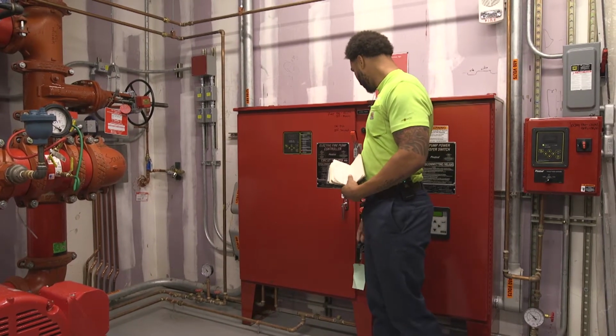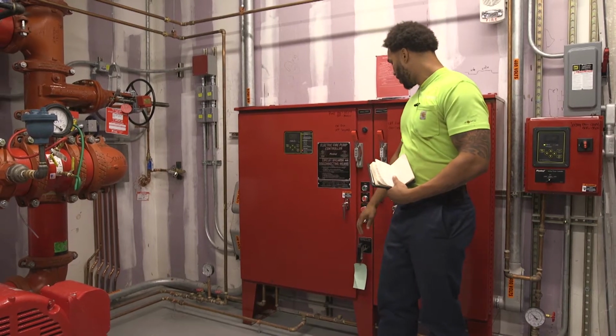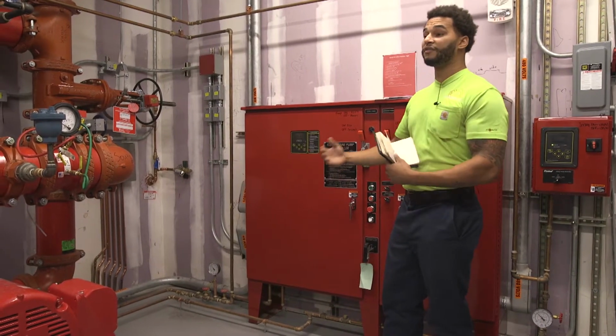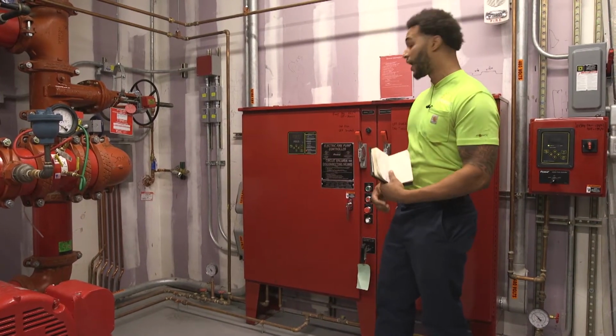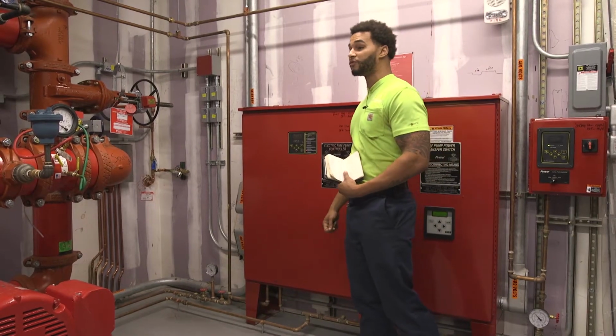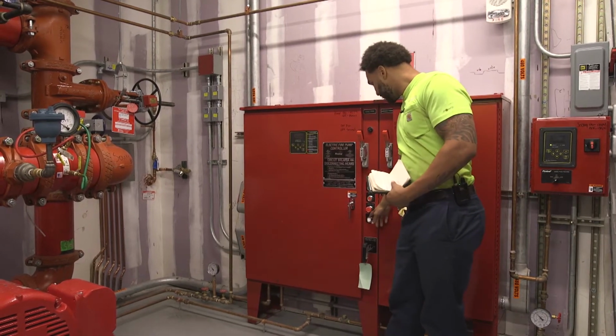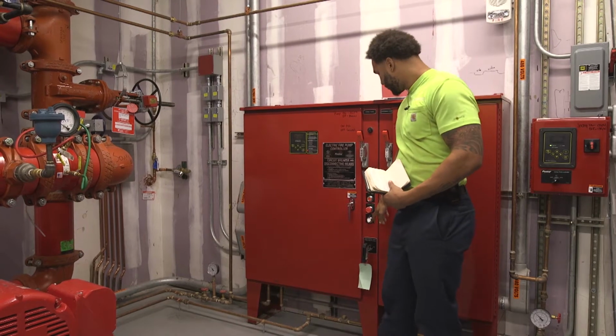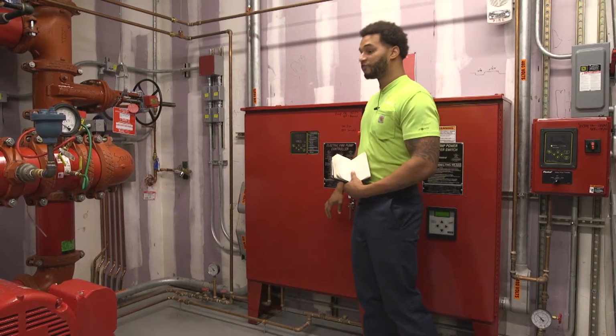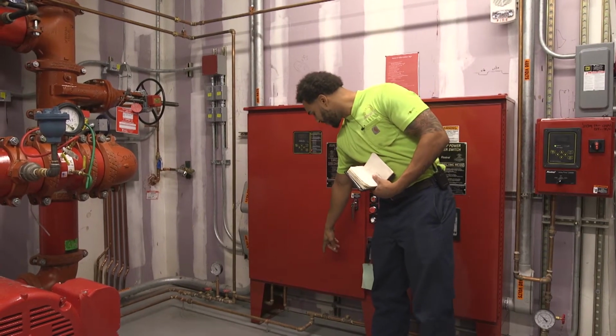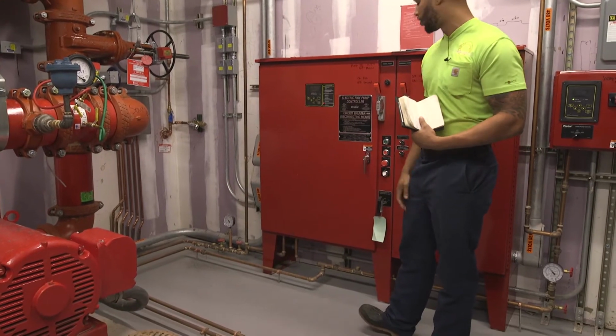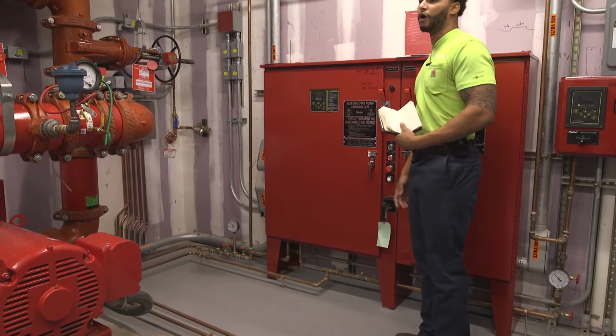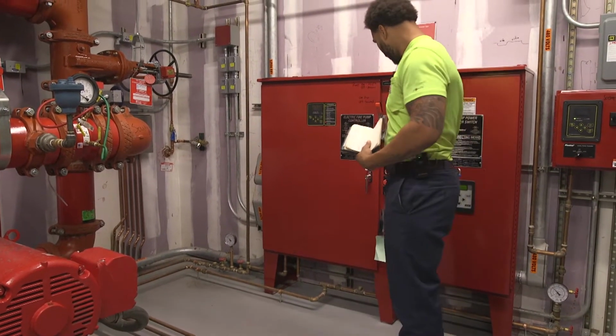Our emergency stop button here, you push this button and it's going to bypass that soft start and soft stop, so it's going to quickly stop this fire pump. This touch button here, you push this button and it's going to simulate loss of pressure. We're going to drop pressure there at the drain and the fire pump is going to kick on. So this is basically a simulation of pressure loss in the system.